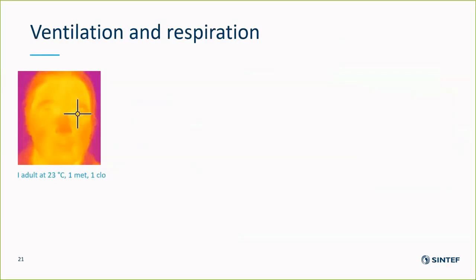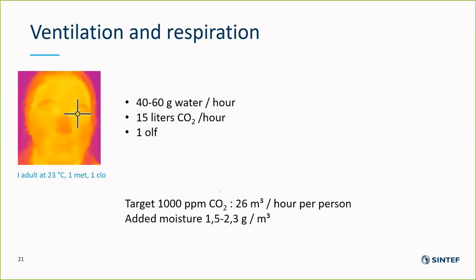Respiration is a free source of moisture. My colleague Kari, wearing one met and one clo, will probably evaporate about 40 to 60 grams of water per hour, along with 15 liters of CO2 and one olfactory unit. So if we ventilate to achieve a CO2 level at 1000 ppm, we will perhaps be able to add 1.5 or a little more grams per cubic meter to the air, which will increase the moisture level without obviously impairing the indoor air quality.